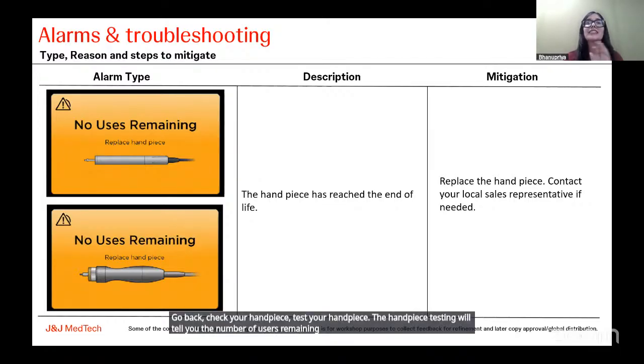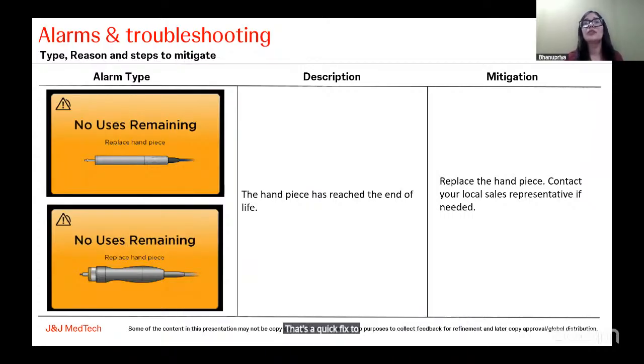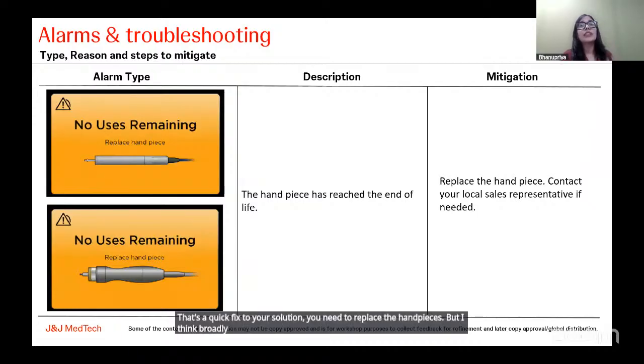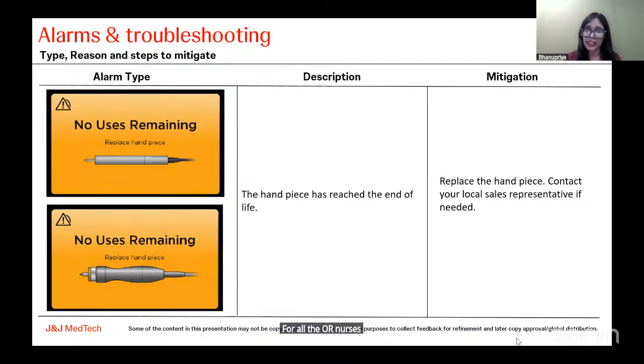And if it says that there's 0 uses remaining, that's a quick fix to your solution. You need to replace the handpieces. But I think broadly, the reason for the majority of the errors is also the cleaning protocols of your end effectors. We regularly do a program, and I believe a lot of other companies might also be doing, called the in-service protocol program for all the OR nurses and all the OT technicians. And we recommend doing this every quarter.